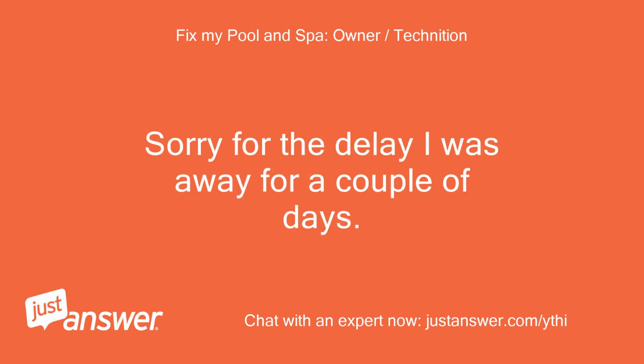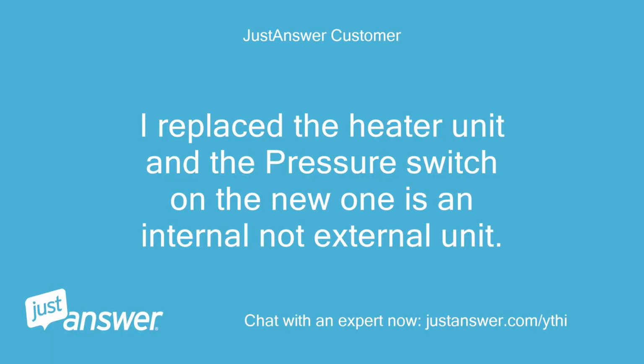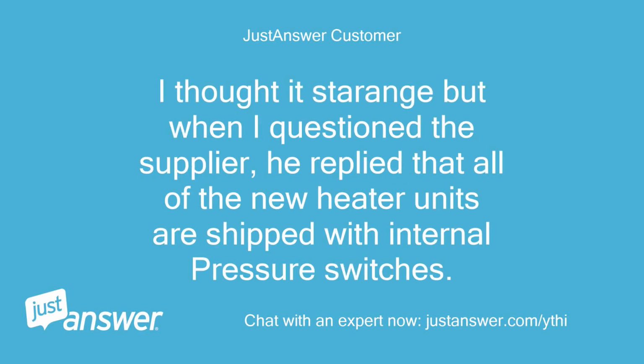Sorry for the delay, I was away for a couple of days. I replaced the heater unit and the pressure switch on the new one is an internal, not external unit. I thought it's strange, but when I questioned the supplier, he replied that all of the new heater units are shipped with internal pressure switches.